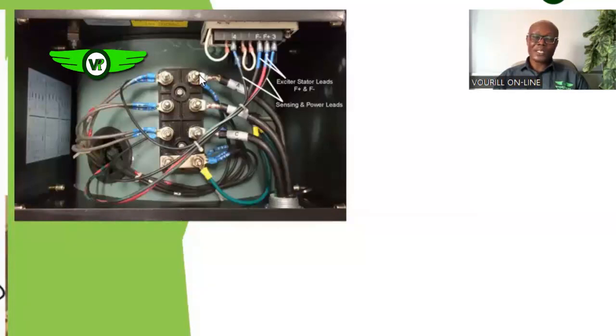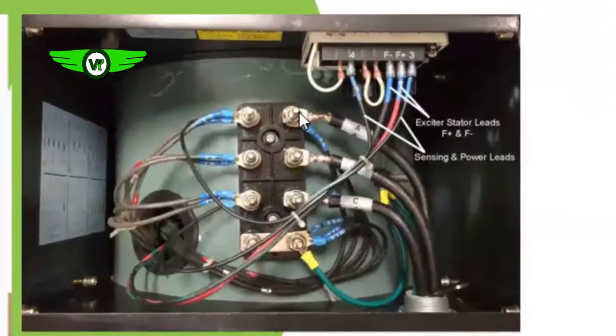So when the generator is working, you take your digital multimeter to the AC volt selection. When you probe between the phases, say line 1, line 2, you are supposed to have 415 volts. Line 2, line 3, you are supposed to have also 415 volts. Then line 3, line 1, you are also supposed to have 415 volts.